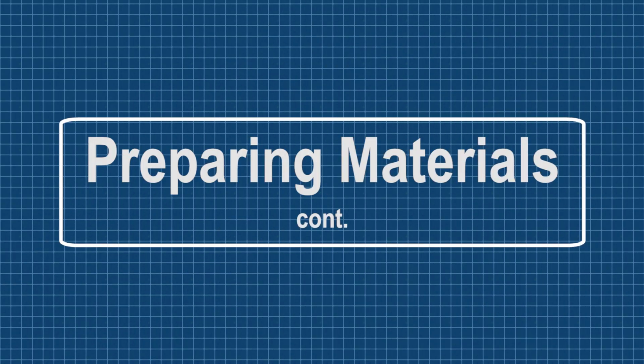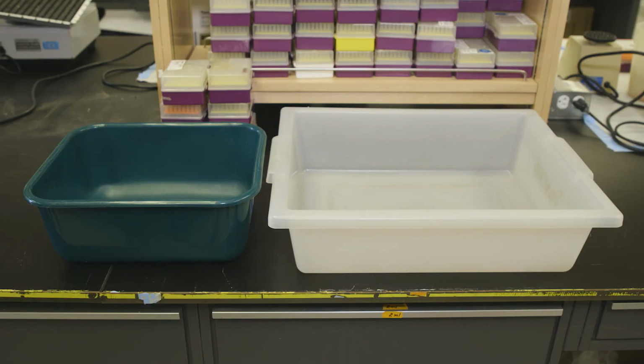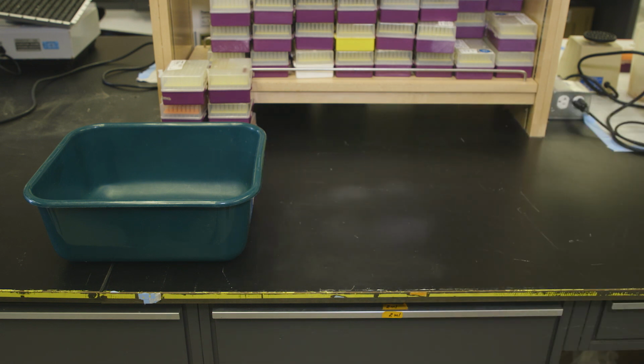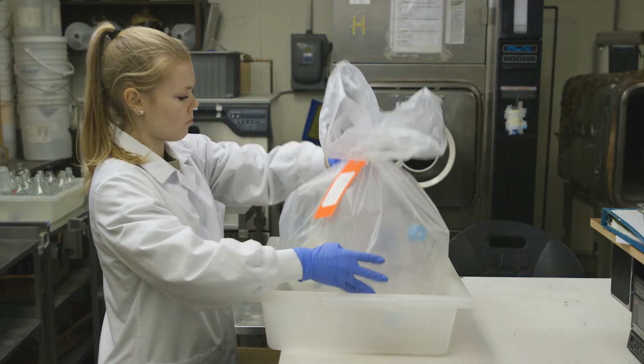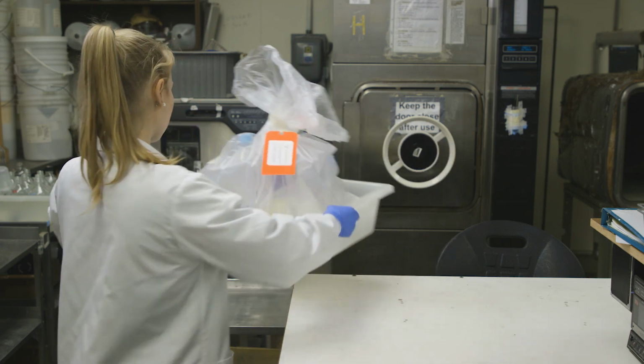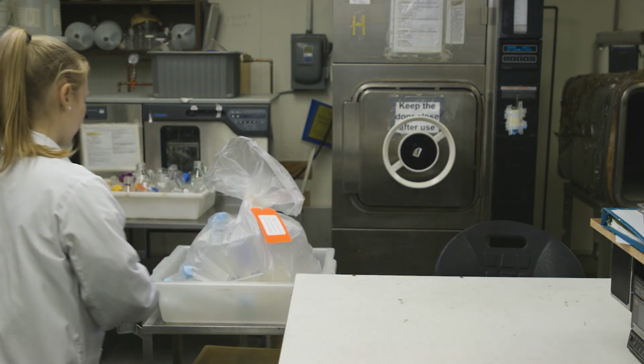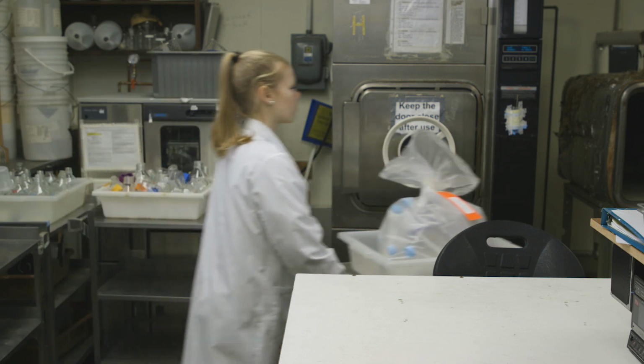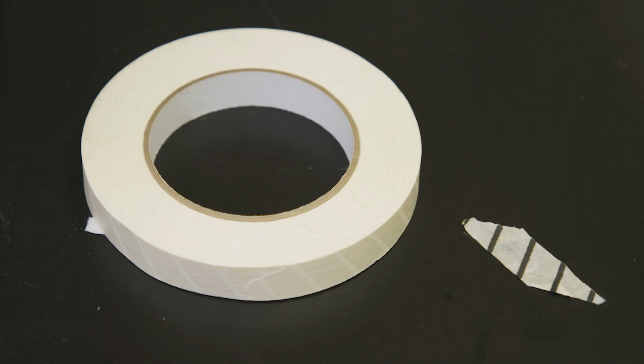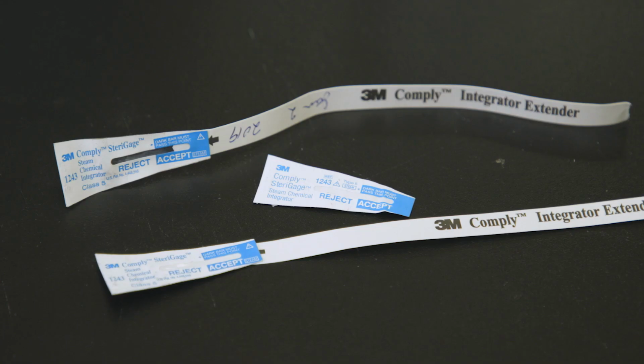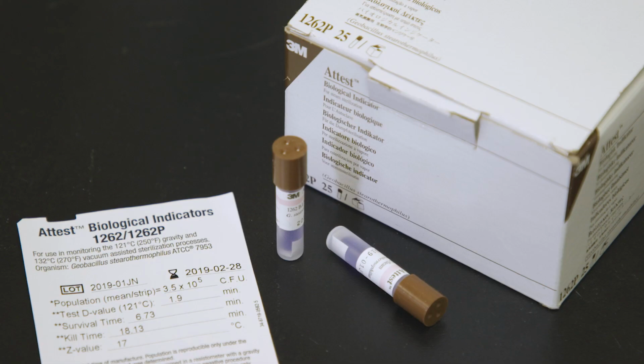Now that you've determined your items are autoclave safe, you must prepare and package the materials correctly so that they are properly sterilized and do not damage the autoclave during operation. First, you must acquire an autoclave safe bin. The bin must be large enough to contain all contents in the event of a boil-over, spill, or leak. You must also acquire a method to verify that the autoclave sterilized its contents. To do this, you will need autoclave tape or chemical indicators, chemical integrator strips, and biological indicators.